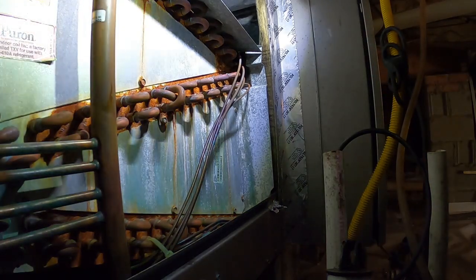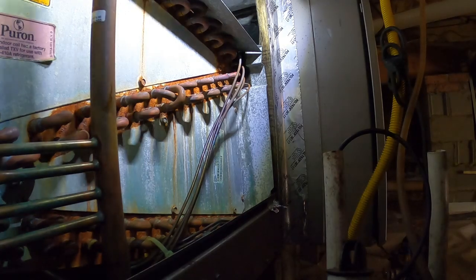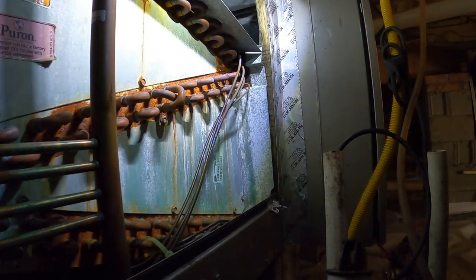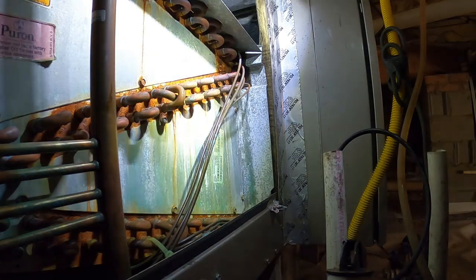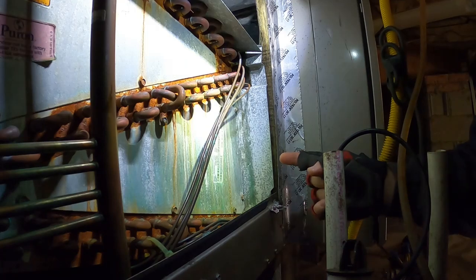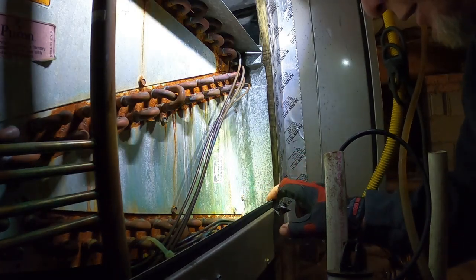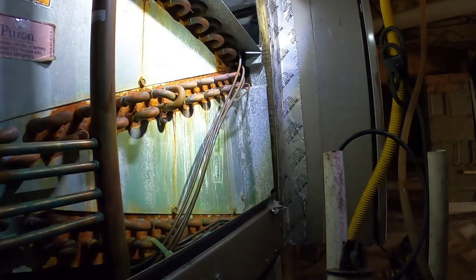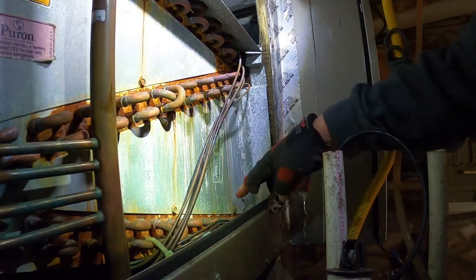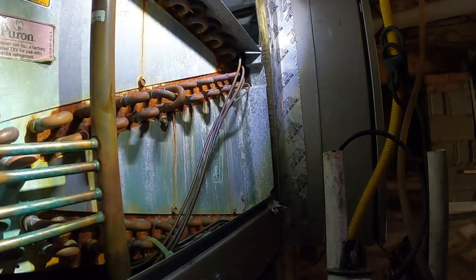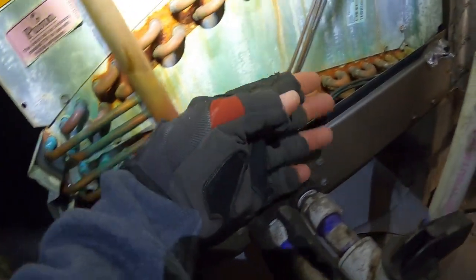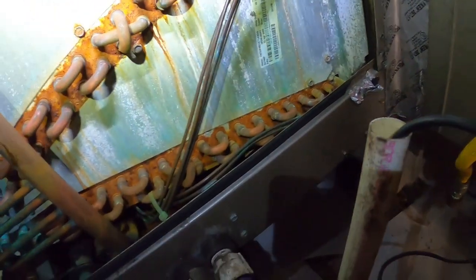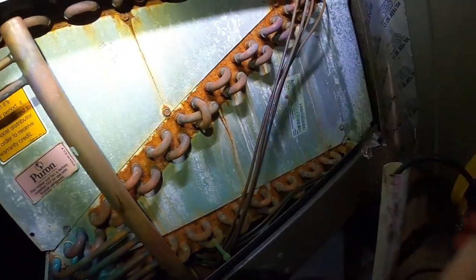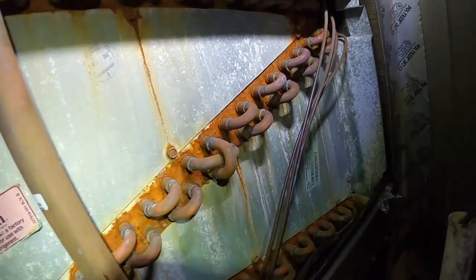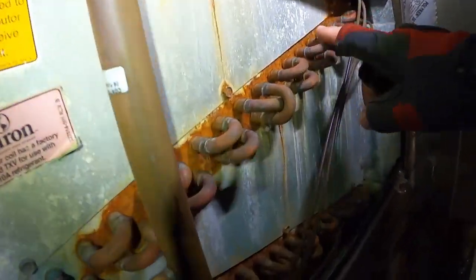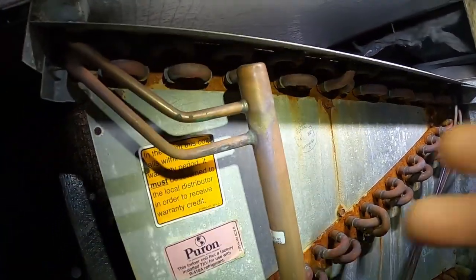Well, that was fun. Because I only recorded about the last 10 minutes of me doing this thing. I've been working on this coil for the last 30 minutes trying to find that leak, and finally - I don't know if it's on the back side of those fins or if it's on this side. I don't see any oil down there, but it's definitely leaking back there. It could be on the other side, back behind there. I can't get my arm all the way back under the bottom of this thing to get all the way back there, unfortunately. And I could pull this plate out if I wanted to, I guess, but I'm not going to all that trouble. There's a leak in it, I'm picking it up. This thing's rusted, it's 17 years old. I'm going to call and get her a price on the coil.